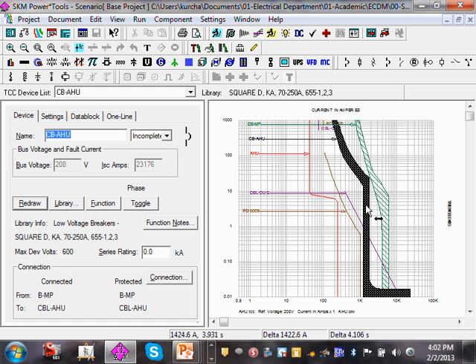Overload. Thank you. So what's going to protect you right at this level, from just that little thing here that we're not showing, is the overload, because that's an air handling unit. And air handling units have overload, and your overload is set to 20 seconds or so. So right in these levels, the overload would be able to protect it. You want the breaker to trip fast before the conductor catches fire. So that's why that conductor, by the way, was way oversized.